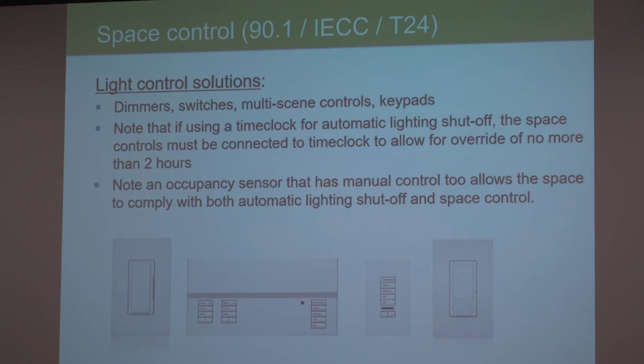All right. One important thing, though, is remember the automatic shut-off? You can't override the shut-off by more than 2 hours. So if you're doing a time clock for your shut-off, you've got to make sure that the manual controls are connected to that time clock so that if the automatic shut-off sweeps the lights off and an occupant turns the lights back on, that override can't last more than 2 hours.